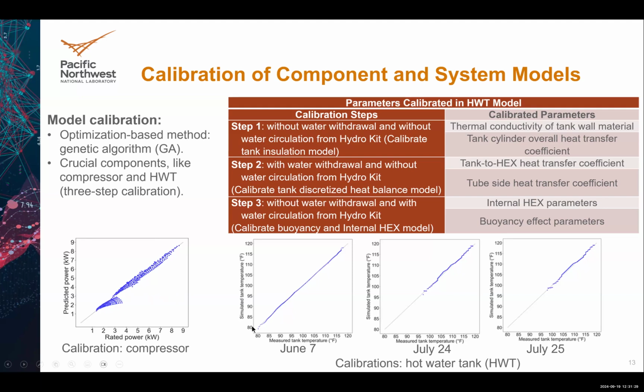0.9. Meanwhile, if you look at these 3 figures, those are different days in June and July. The x-axis is the measured tank temperature. The y-axis is the simulated tank temperature. So you can see the calibration works. The measured temperature has a very good fit with the simulated temperature. So that means we have calibrated the critical components.